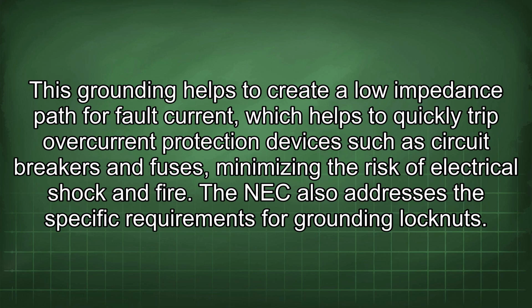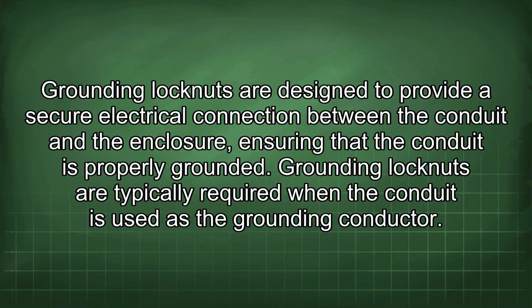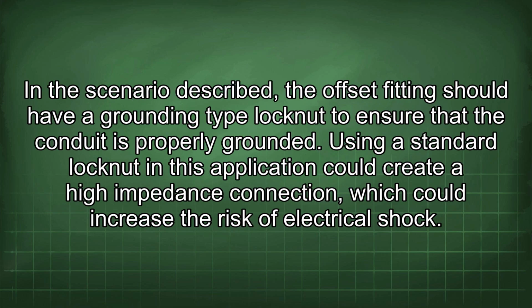The NEC also addresses the specific requirements for grounding locknuts. Grounding locknuts are designed to provide a secure electrical connection between the conduit and the enclosure, ensuring that the conduit is properly grounded. Grounding locknuts are typically required when the conduit is used as the grounding conductor. In the scenario described, the offset fitting should have a grounding type locknut to ensure that the conduit is properly grounded. Using a standard locknut in this application could create a high impedance connection, which could increase the risk of electrical shock.